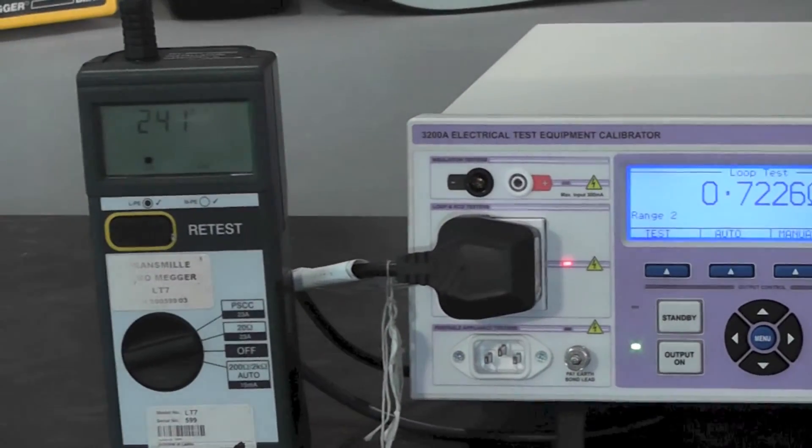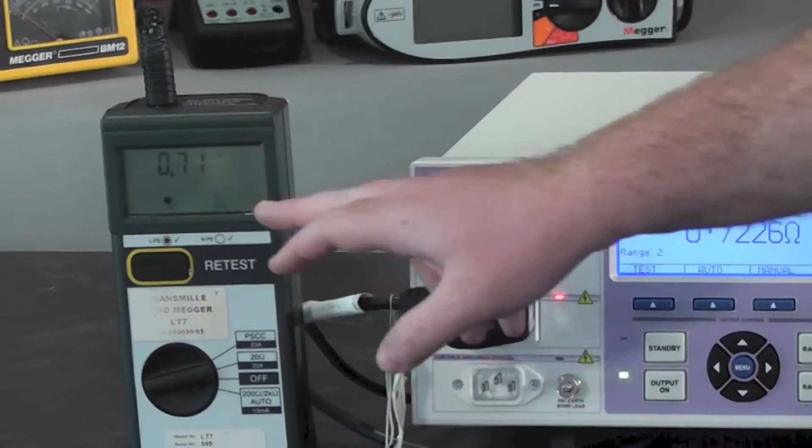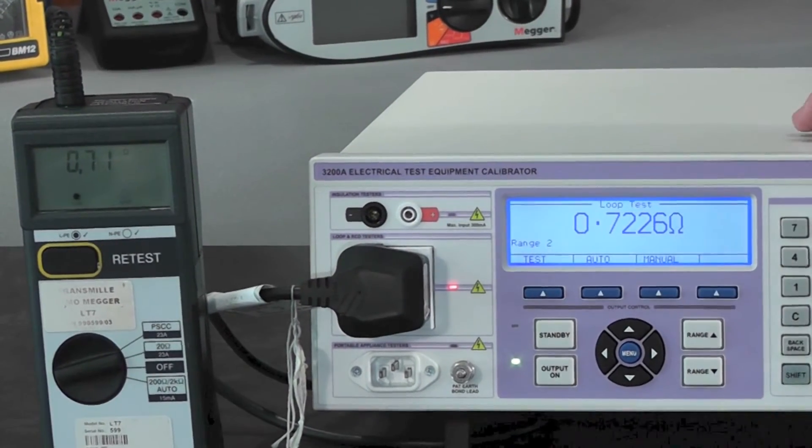After waiting for the loop tester to initialize, compare the recorded result from the loop tester against the indicated value on the 3200A.